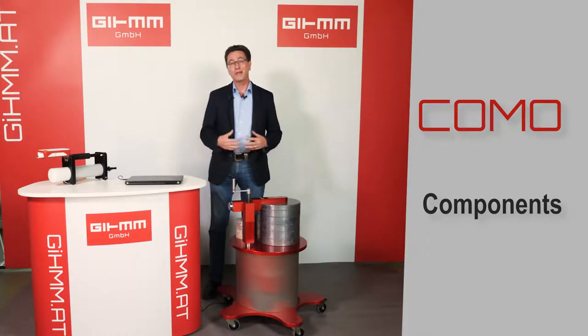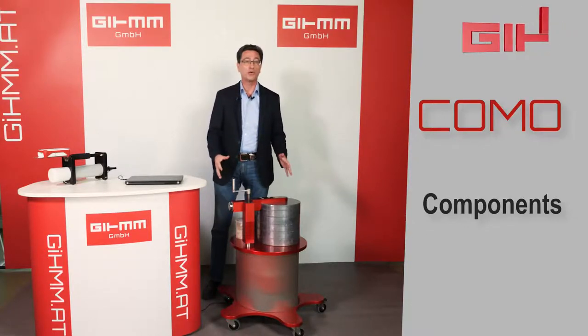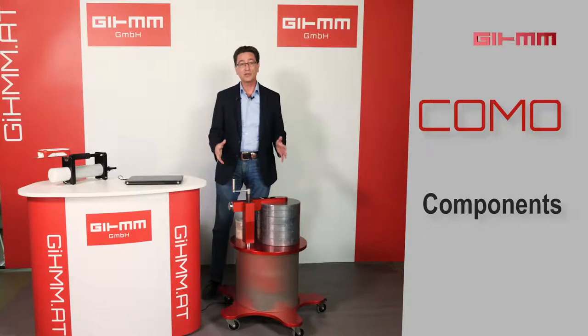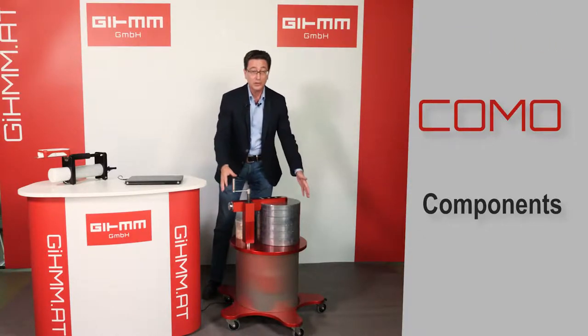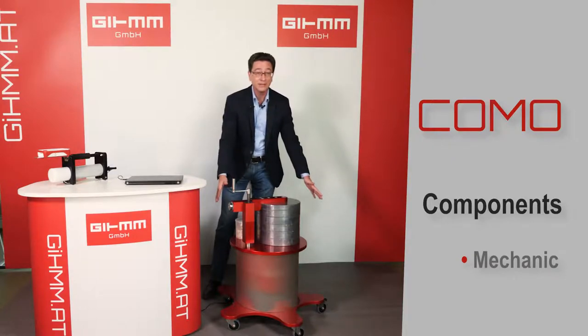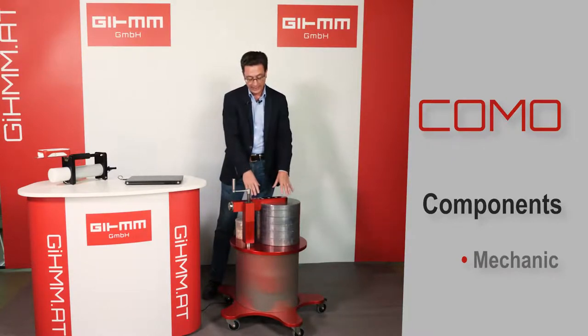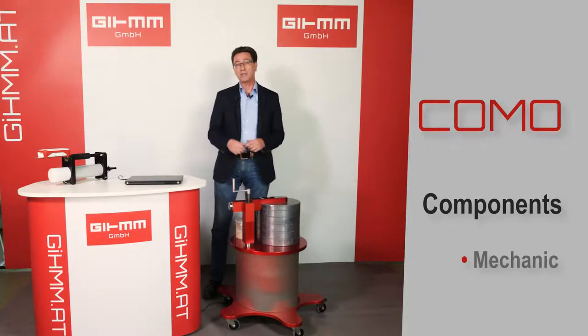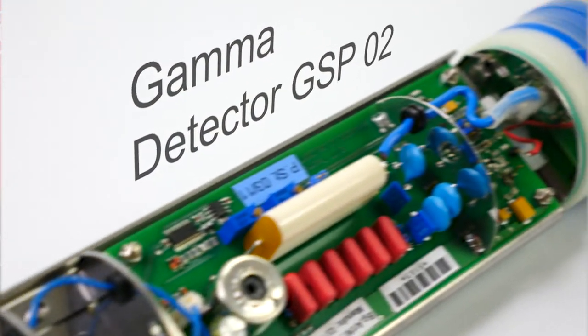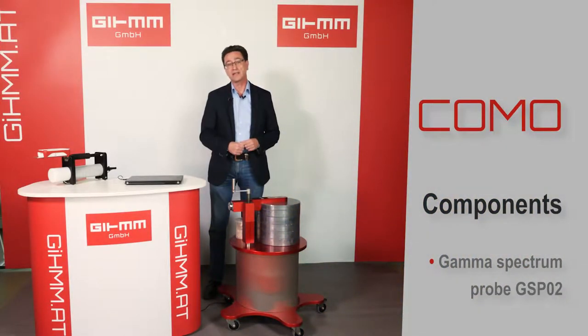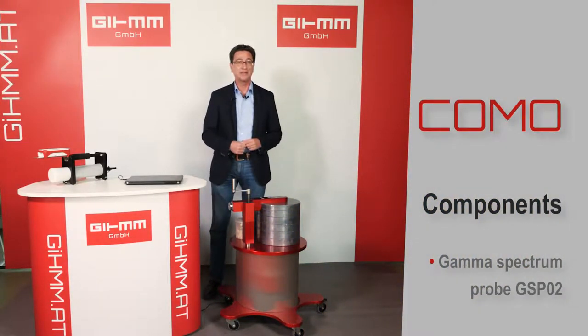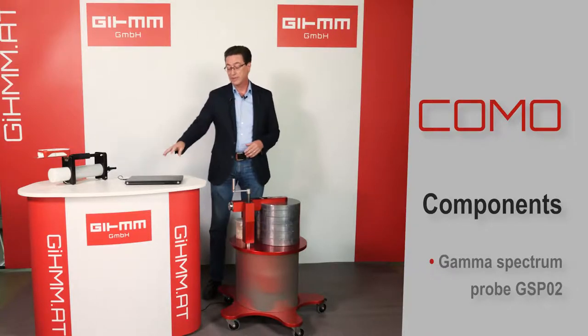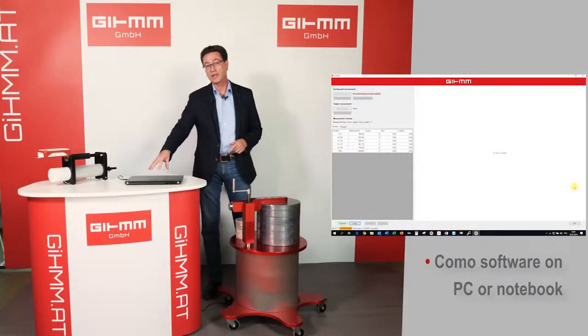Before I show you now how to measure any sample, let's have a look at the parts of our COMO monitoring system. The COMO, in fact, consists of three main parts. First, the COMO mechanic, which you can see here. Second, inside of the measuring chamber, we have our gamma spectrum probe, GSP02, for which we usually use a 3-inch sodium iodide scintillator. And third, we run our COMO software on any Windows PC or notebook, at least from version 7 upwards.